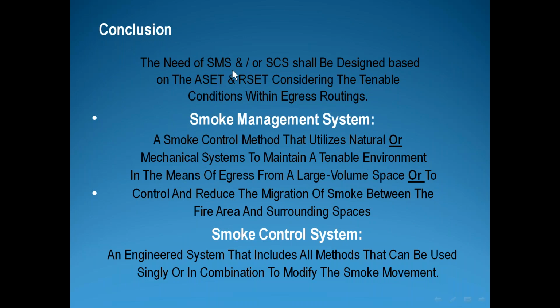So the conclusion is the need for a smoke management system and or smoke control system. Here there is a little bit of difference. It shall be designed based on the available safe escape time and the required safe escape time, whichever is greater, and we can adapt it by our mechanical systems, considering the tenable conditions within the egress routing. Here, the smoke management system, in general, if we want to talk about it after knowing adequate information about the ignition, about the flame propagation, about the doors, about the fire alarm, about the response time of the sprinklers and the detector systems, okay, you can design the smoke management system in a proper way.